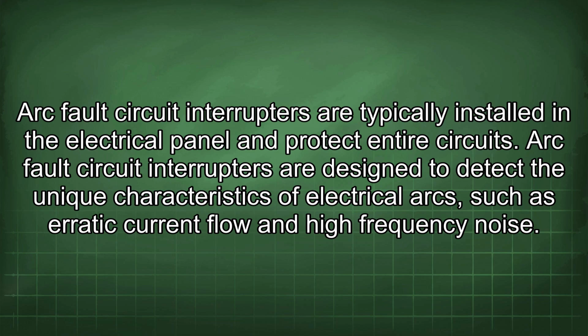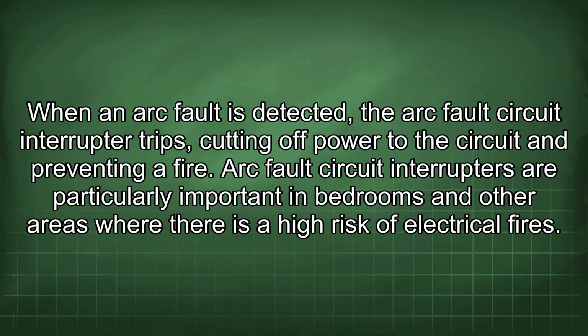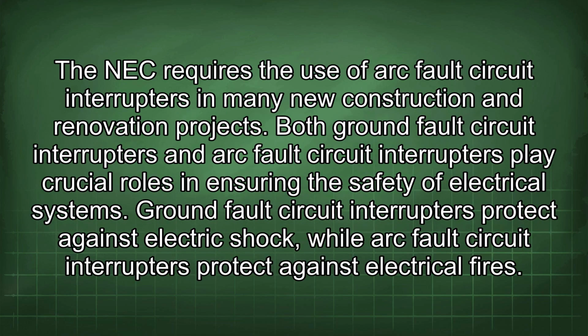Arc fault circuit interrupters are designed to detect the unique characteristics of electrical arcs, such as erratic current flow and high-frequency noise. When an arc fault is detected, the arc fault circuit interrupter trips, cutting off power to the circuit and preventing a fire. Arc fault circuit interrupters are particularly important in bedrooms and other areas where there is a high risk of electrical fires. The NEC requires the use of arc fault circuit interrupters in many new construction and renovation projects. Both ground fault circuit interrupters and arc fault circuit interrupters play crucial roles in ensuring the safety of electrical systems.